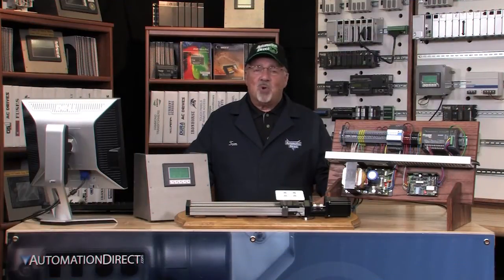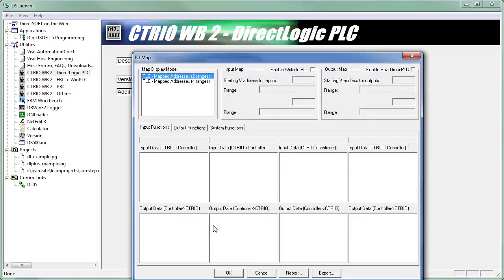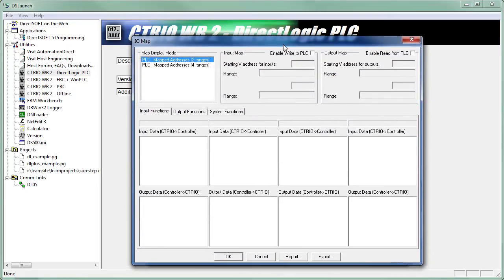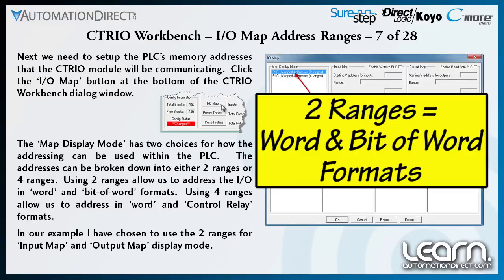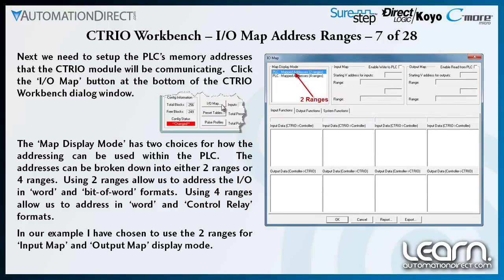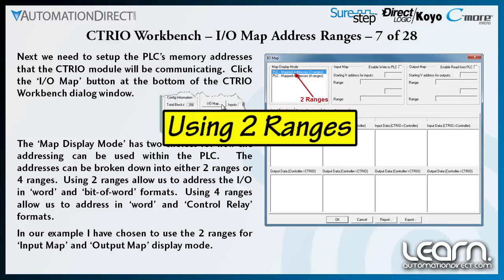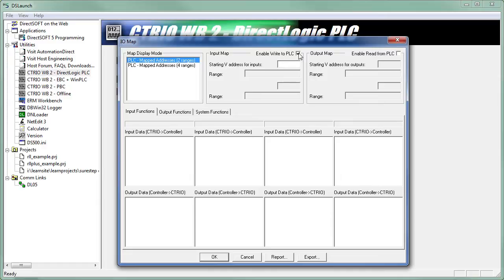Next, I'll set up the PLC's memory addresses that are used to communicate with the CTRIO module. I click the I/O Map button at the bottom of the CTRIO Workbench dialog window. In the I/O Map dialog window, I have two choices under the Map Display mode: addresses can be broken down into either two ranges or four ranges. Using two ranges allows addressing the I/O in Word and Bit of Word formats; four ranges allow addressing in Word and Control Relay formats. I have chosen to use the two ranges for my input and output map display modes. I check the Enable Write to PLC box and enter Memory Register V2400 for the starting V address for inputs.